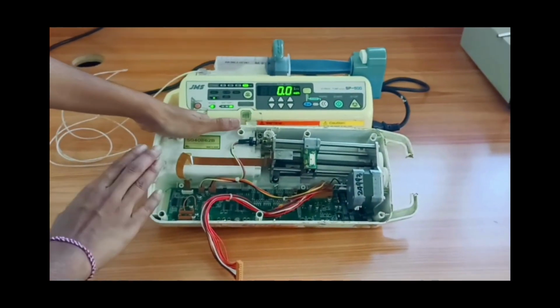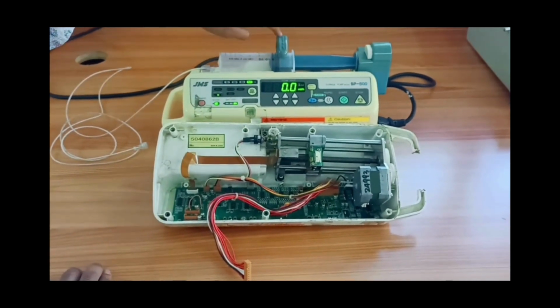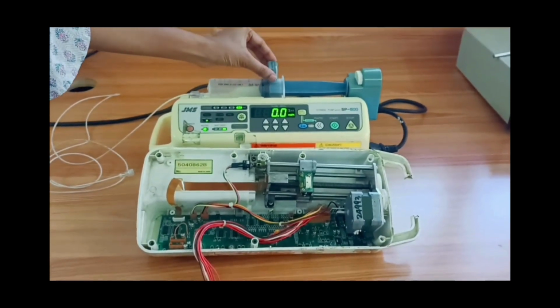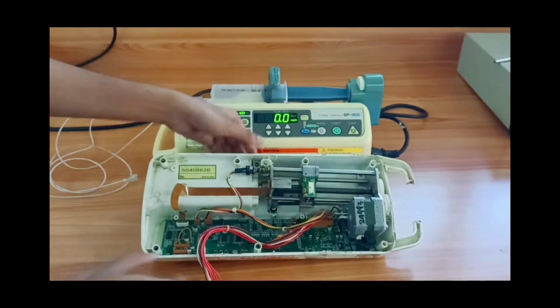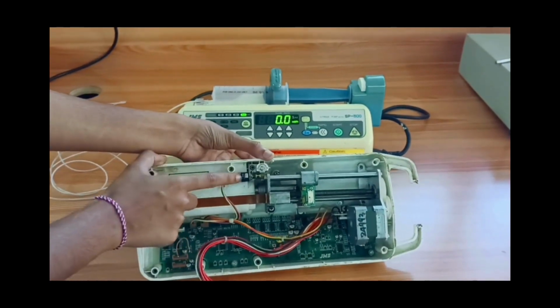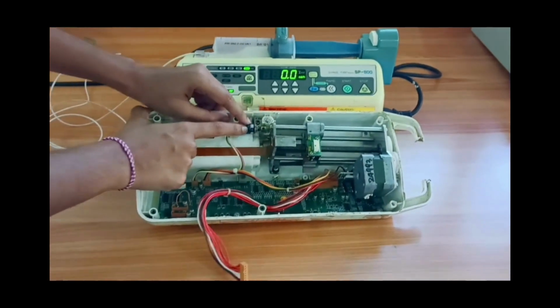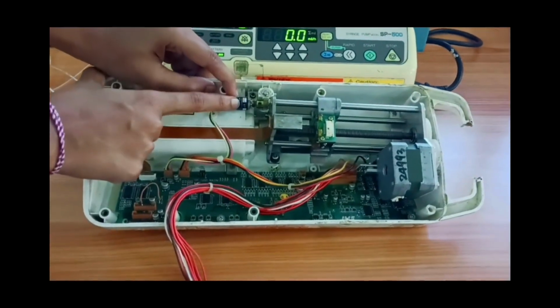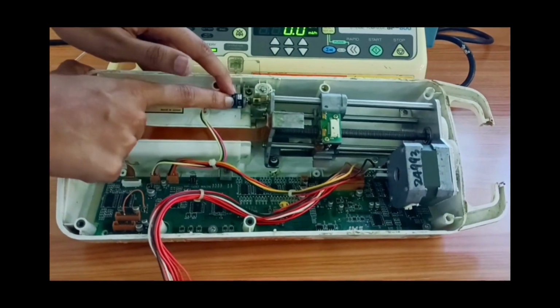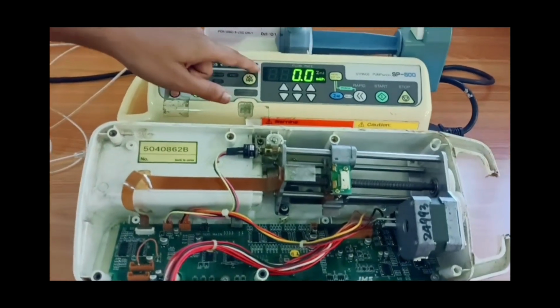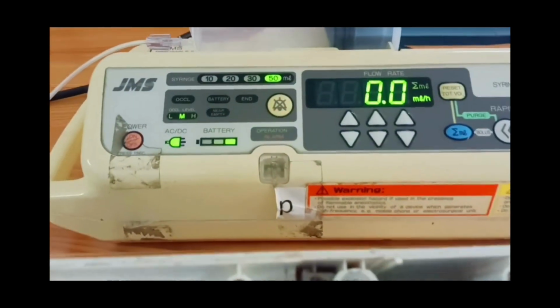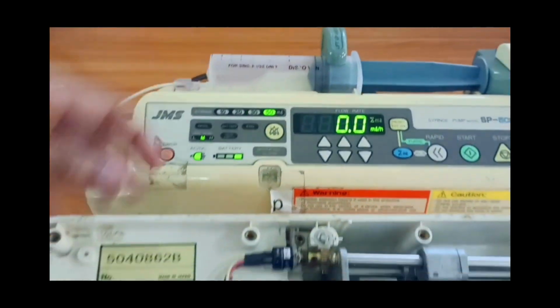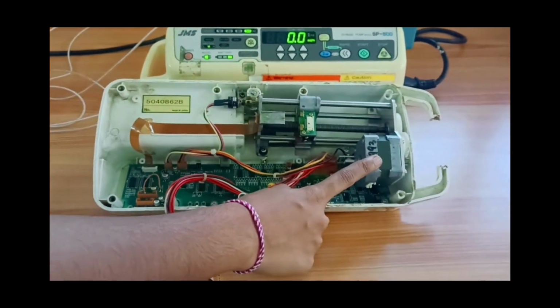Now let us look at the internal parts of the syringe pump. As we already know, this is the syringe barrel detector, which can move up and down. While it is moving up and down, it is connected to the potentiometer. When it moves, the resistance of the potentiometer changes. As a result, the changed resistance will be displayed in the form of the amount of fluid that the syringe holds.